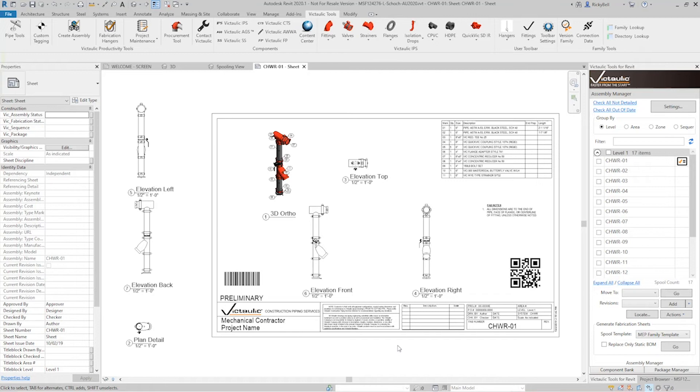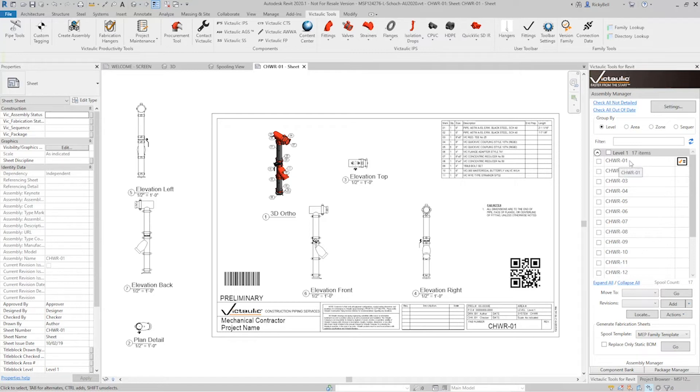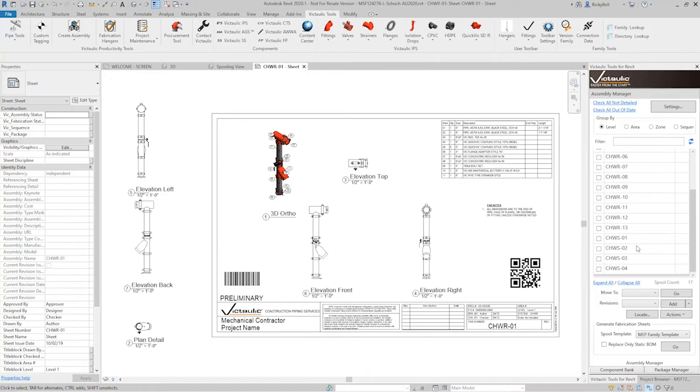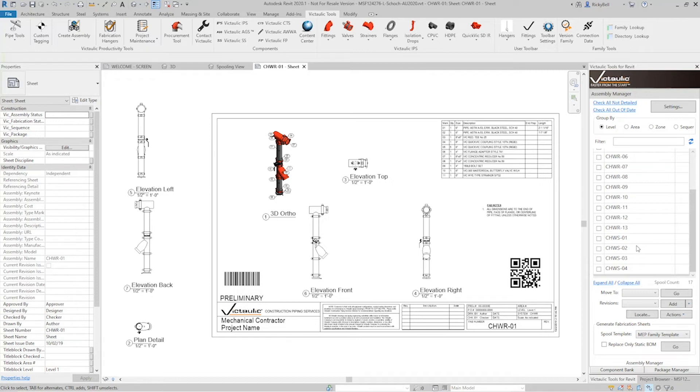It's important to note even over here in the assembly manager, the numbering of the assemblies that were created has a little bit of logic that goes with it as well. I gave it a starting number of one and you see it started with chilled water return. It went all the way up to number 13 there before it found the supply line. And when the supply line came in, it started back over at number one. So that's your best bet. You started a low number with the auto assembly. It's going to use that as a starting number for each iteration of different prefixes. So in my case, the prefix was a system abbreviation. In your case, it could be the level plus the system abbreviation, whatever you really select as a prefix. But these numbers will start back over at one.